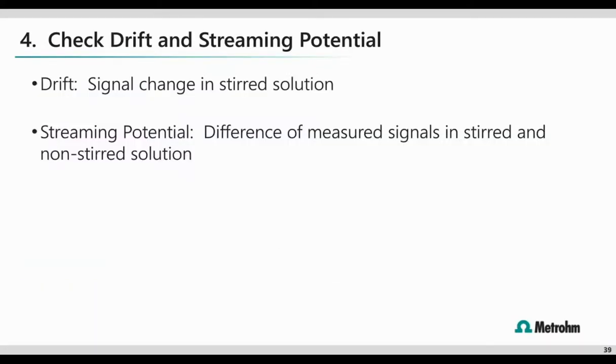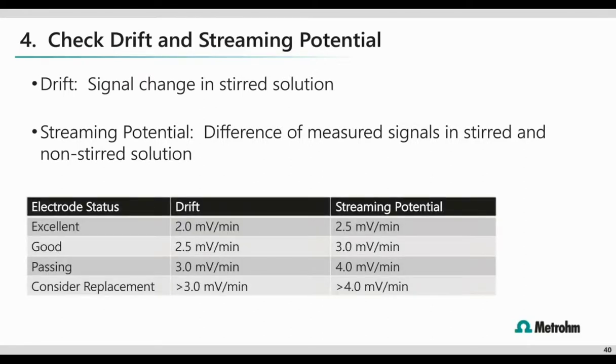Number 4, check drift and streaming potential. Drift is a signal change in a stirred solution over a period of time. We usually recommend 3 minutes. The streaming potential is the difference of measured signals in a stirred solution versus a non-stirred solution. For each electrode status, I've listed the maximum permitted drift in a stirred solution and the maximum streaming potential. Consider electrode replacement if you're observing a drift of greater than 3 millivolts per minute and a streaming potential greater than 4 millivolts per minute.